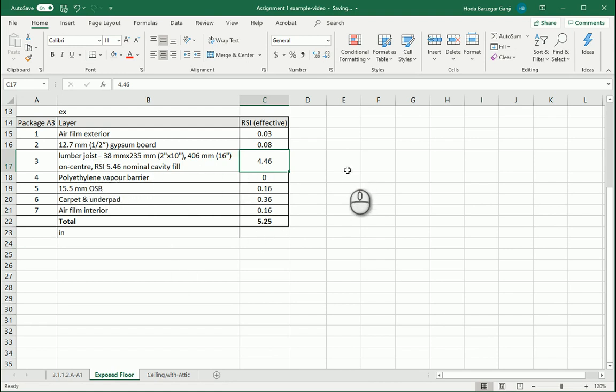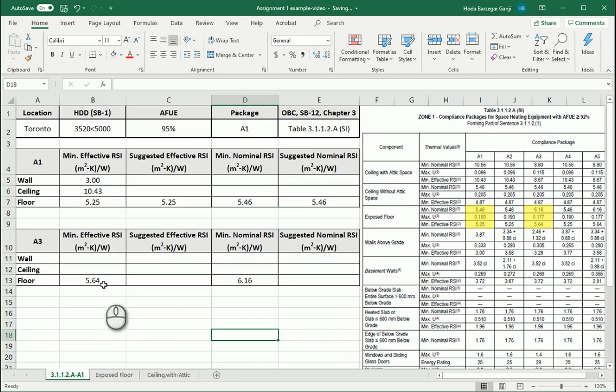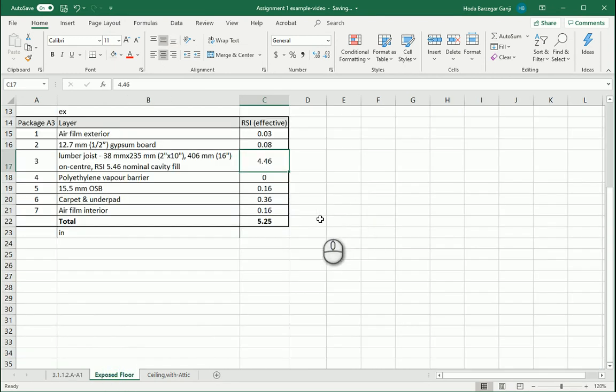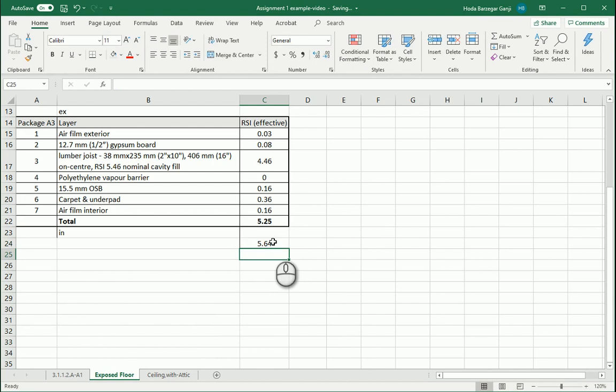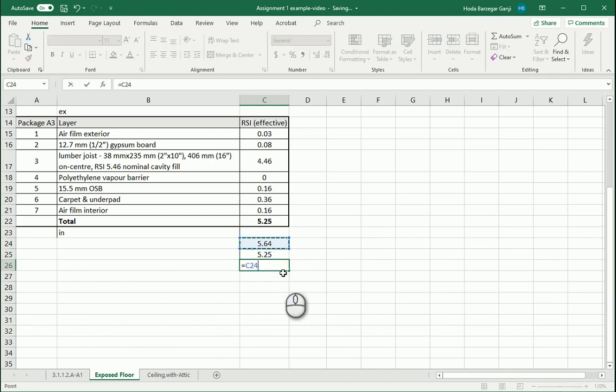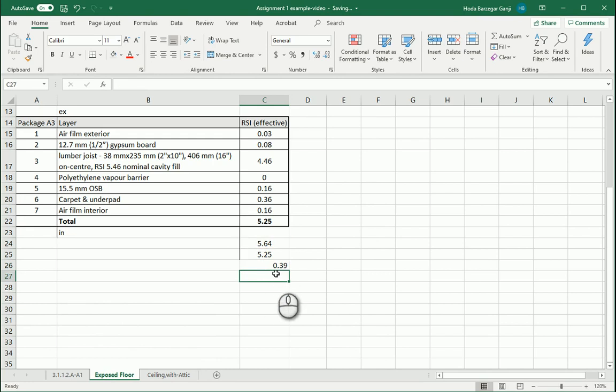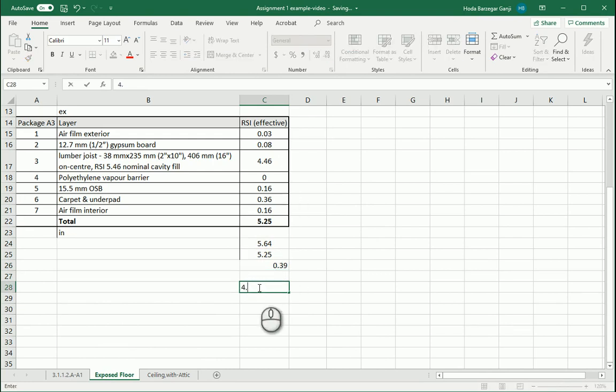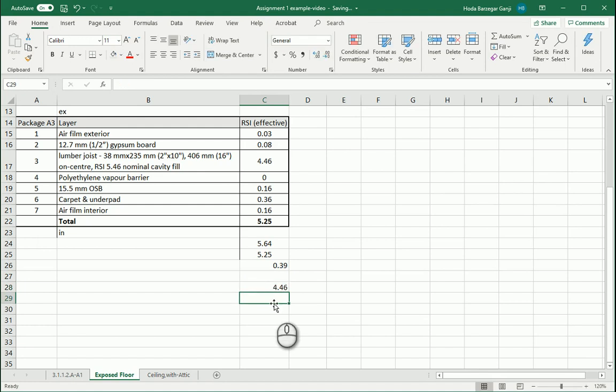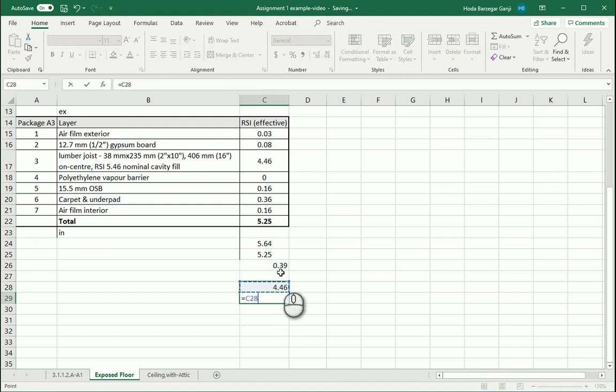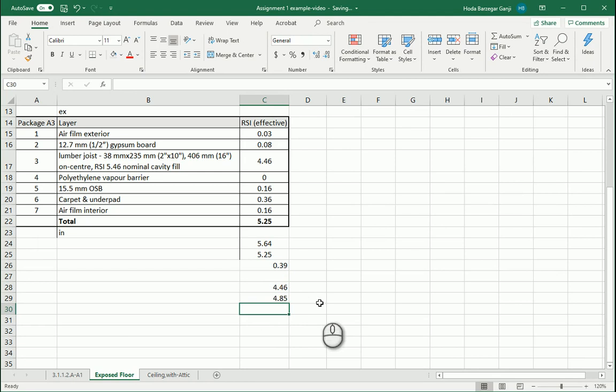We want to get 5.64 at the end, and we have 5.25. The difference between the two values is 0.39. That means to the value 4.46 we need to add that difference, so we should have 4.85 for the effective RSI for this layer.